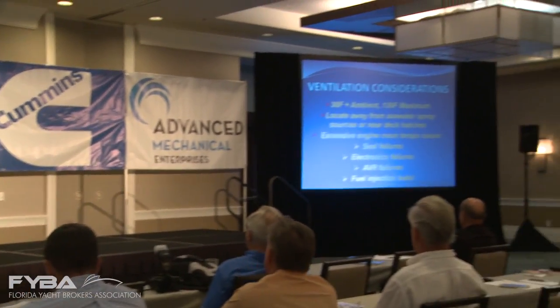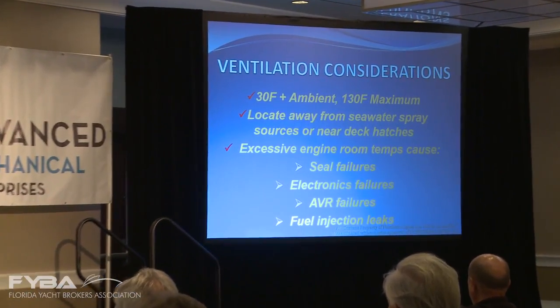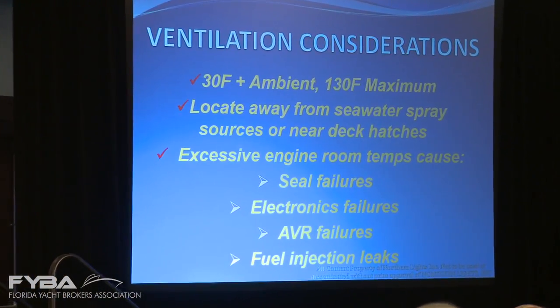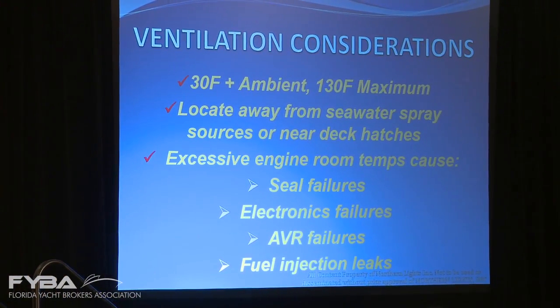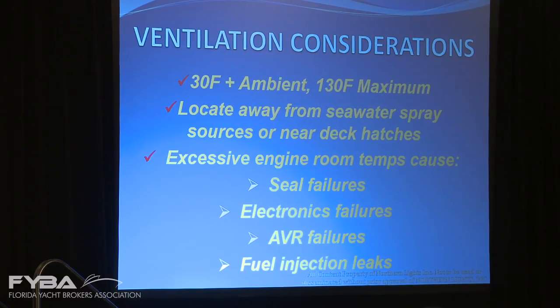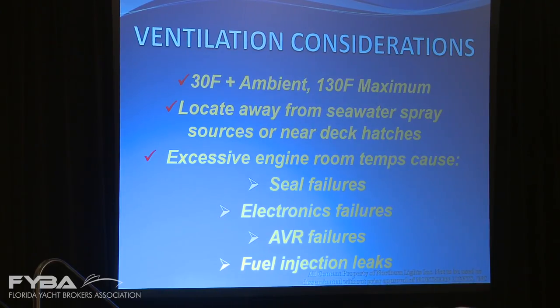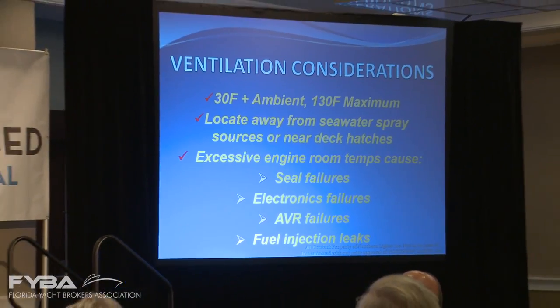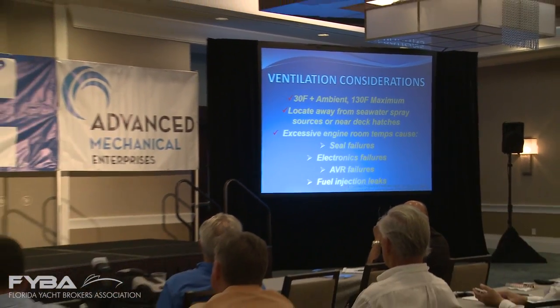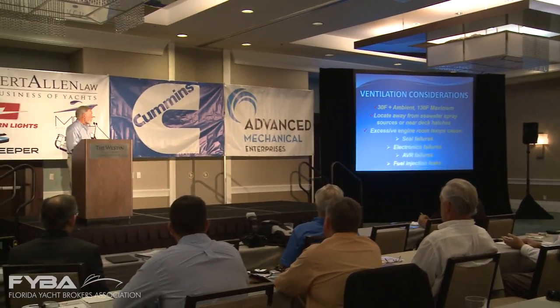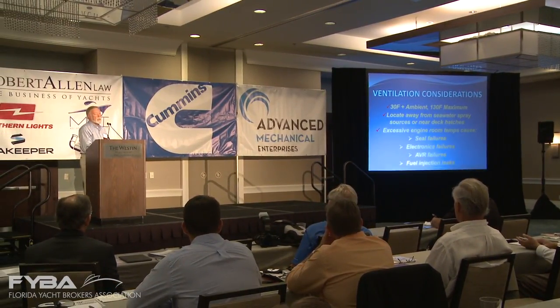Ventilation — our friends mentioned this, and I can't overemphasize it. Most manufacturers go with 30 degrees Fahrenheit above ambient, meaning if it's 70 degrees outside they'd allow the engine room to be no more than 100 degrees inside. 130 Fahrenheit maximum isn't quite a standard, but it's a common one. Some manufacturers don't allow that much temperature, and it's even possible you might have to air condition an engine room to meet their specification.